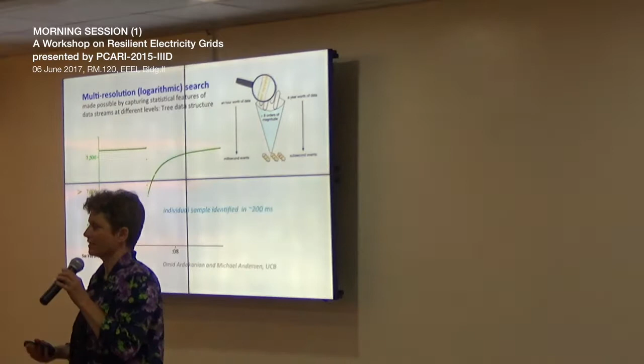A side benefit of making PMU measurements, though it requires much less temporal precision, is that you can synchronize magnitude measurements. One research finding is that even without using synchrophasors per se, there's a lot of value just in having measurements from sensors at different places using the same clock. If you try to use SCADA data, our experience with utilities is that the clocks are never really set correctly.